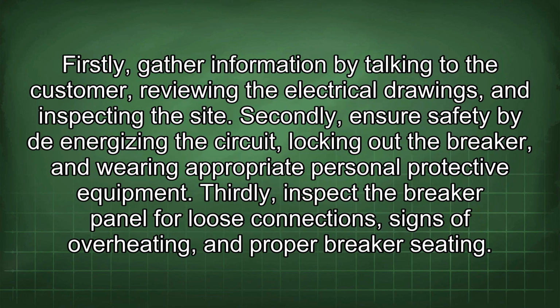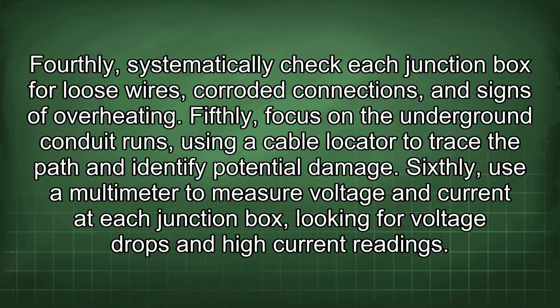Firstly, gather information by talking to the customer, reviewing the electrical drawings, and inspecting the site. Secondly, ensure safety by de-energizing the circuit, locking out the breaker, and wearing appropriate personal protective equipment. Thirdly, inspect the breaker panel for loose connections, signs of overheating, and proper breaker seating. Fourthly, systematically check each junction box for loose wires, corroded connections, and signs of overheating. Fifthly, focus on the underground conduit runs, using a cable locator to trace the path and identify potential damage.